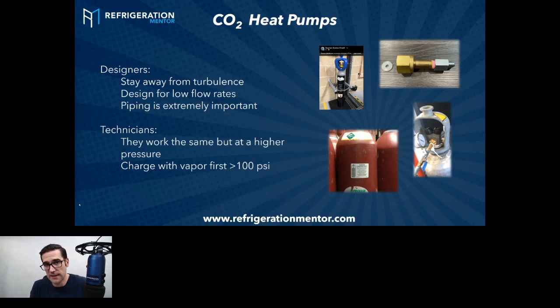After you repair that leak and you pressure test the system, you follow proper pressure test procedures because you want to make sure you should be letting it sit there for 24 hours. I know lots of people don't do that. And you should make sure there's no leak for sure. And then you pull an evacuation down below 300 microns, or 0.3 torr, lower the better. And you want that to hold.